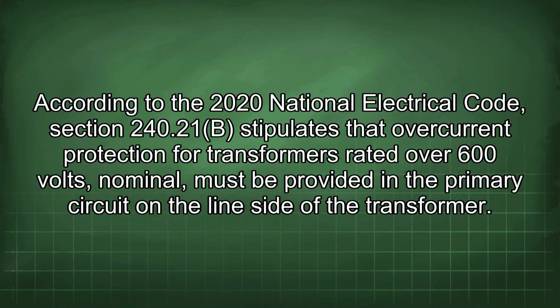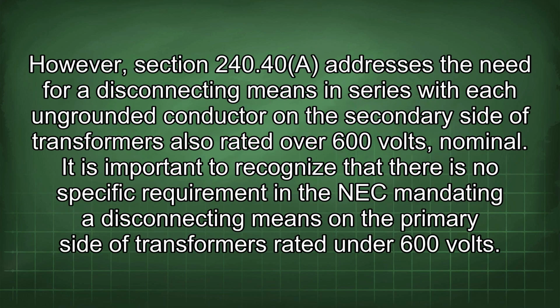According to the 2020 National Electrical Code, Section 240.21(B) stipulates that overcurrent protection for transformers rated over 600 volts nominal must be provided in the primary circuit on the line side of the transformer. However, Section 240.40 addresses the need for a disconnecting means in series with each ungrounded conductor on the secondary side of transformers also rated over 600 volts nominal.